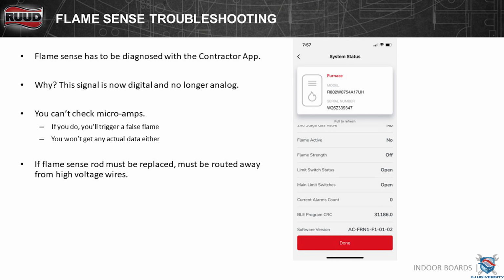So a little bit about the flame sense. The flame sense can no longer be checked with microamps DC. They have changed this to a digital signal now. I want to be 100% transparent with you guys because I've run into this numerous times. There are some issues right now with control boards on furnaces, and it'll give you a fault code saying flame present without gas valve energized.